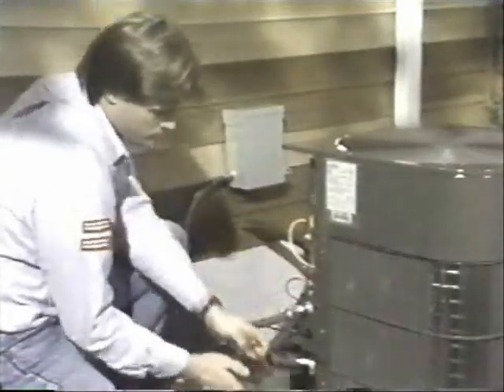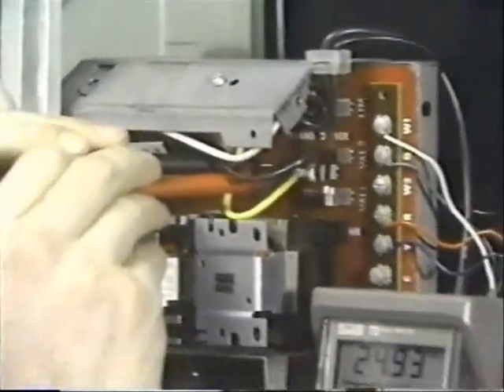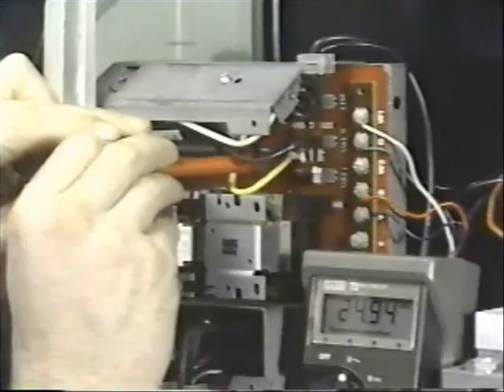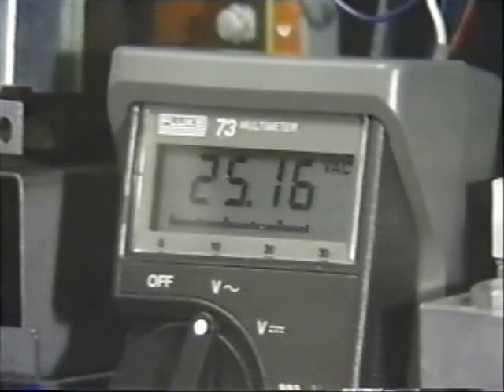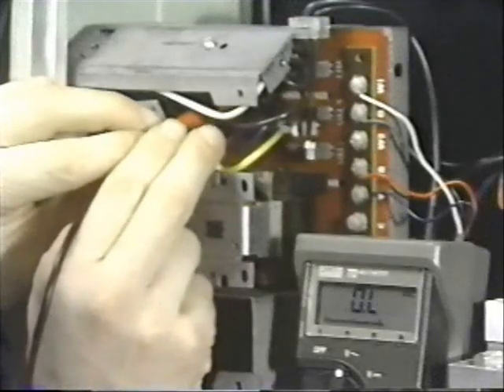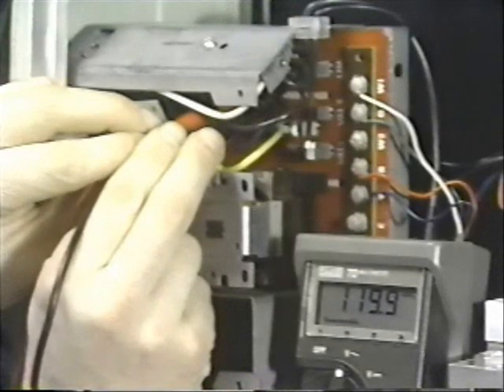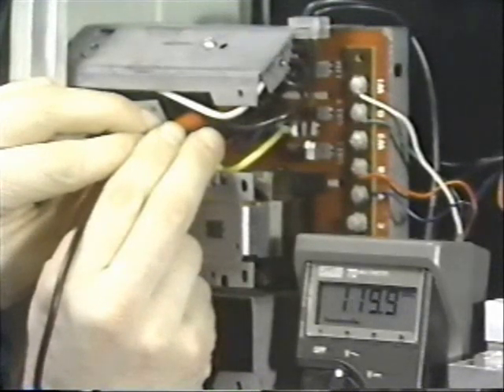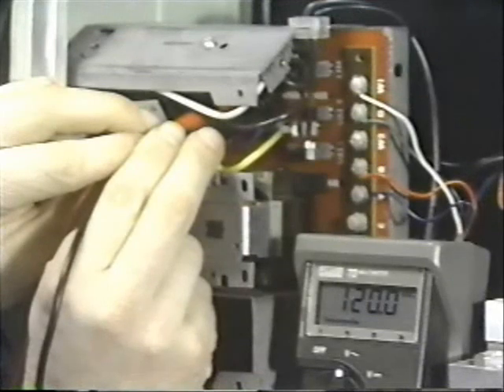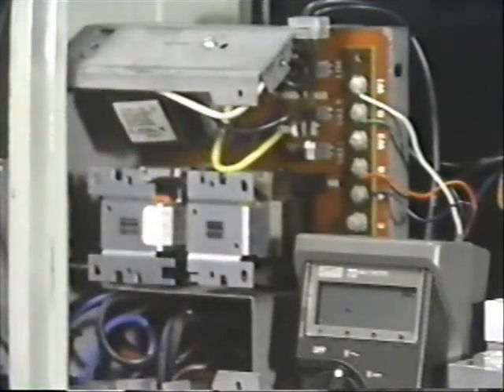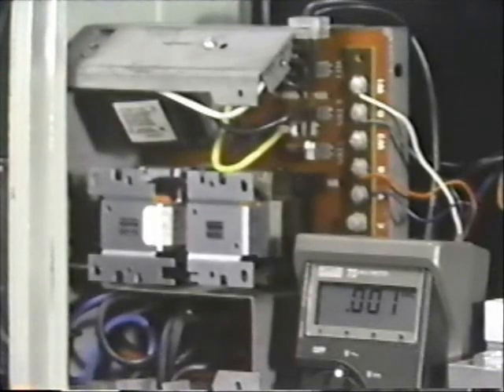Zero voltage means the problem could be in the transformer or somewhere else in the circuit. So check the voltage at the transformer secondary. If it's normal, within 10% of rated voltage, the transformer is okay. If voltage at the secondary is zero, check the line side of the transformer next. Normal voltage going in, but none coming out, means the unit has faulty wiring or is burned out and must be replaced. Now let's go back to the contactor again.